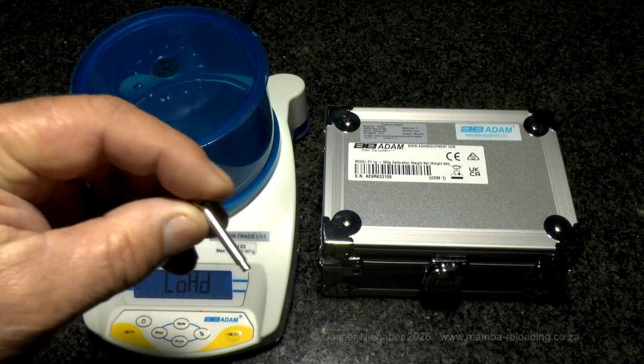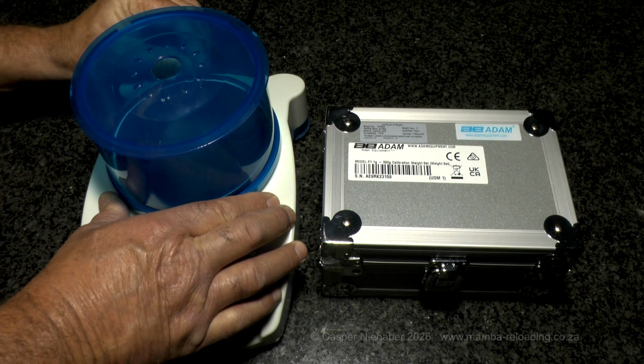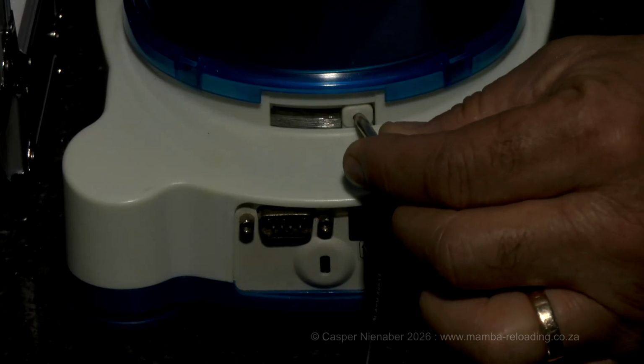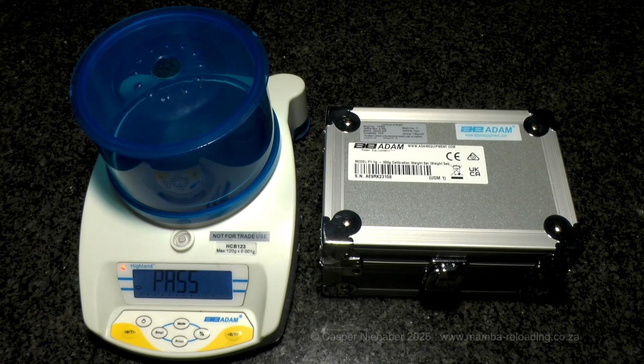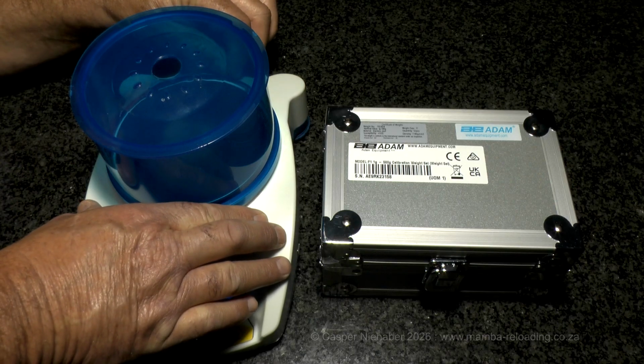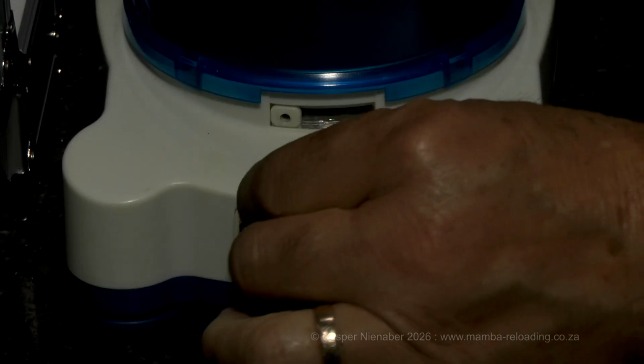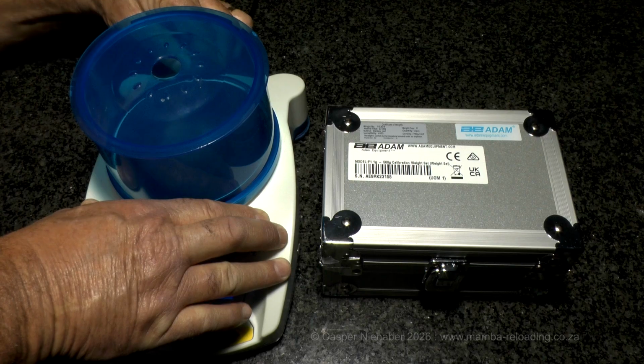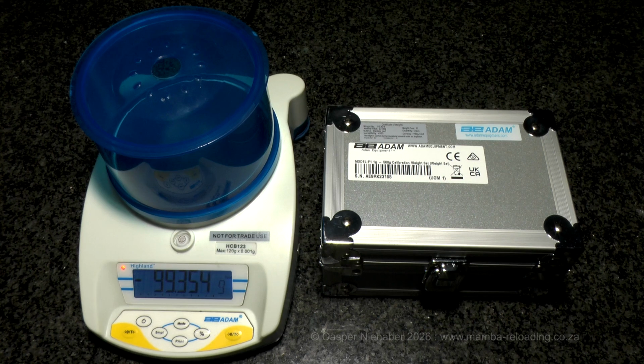Using the supplied handle, carefully lower the internal weight to its lowest position. Press the yellow Zero/Tare button. The display will show Pass, followed by the internal mass value. Press the yellow Zero/Tare button to zero the balance. Using the supplied handle, carefully raise the internal weight to its highest position. The internal mass will now be displayed as a negative value. If this reading closely matches the previous value, it confirms the calibration was successful. Press the yellow Zero/Tare button again to return the balance to zero.